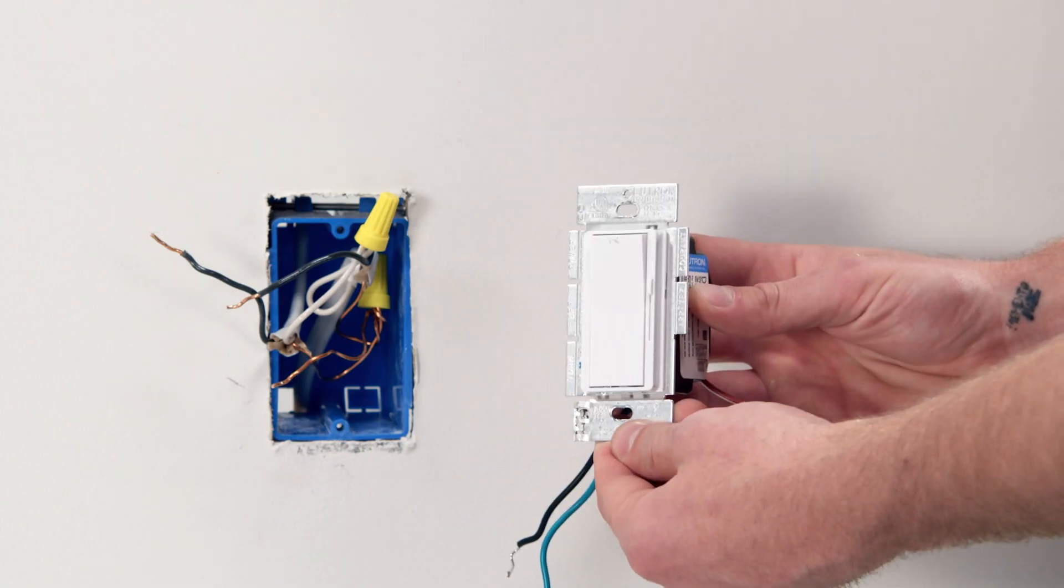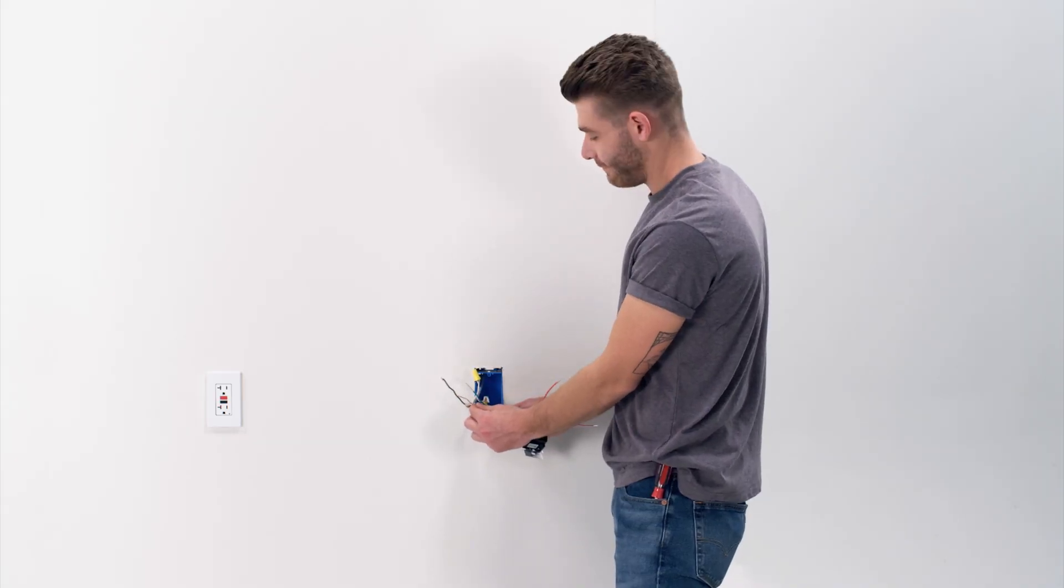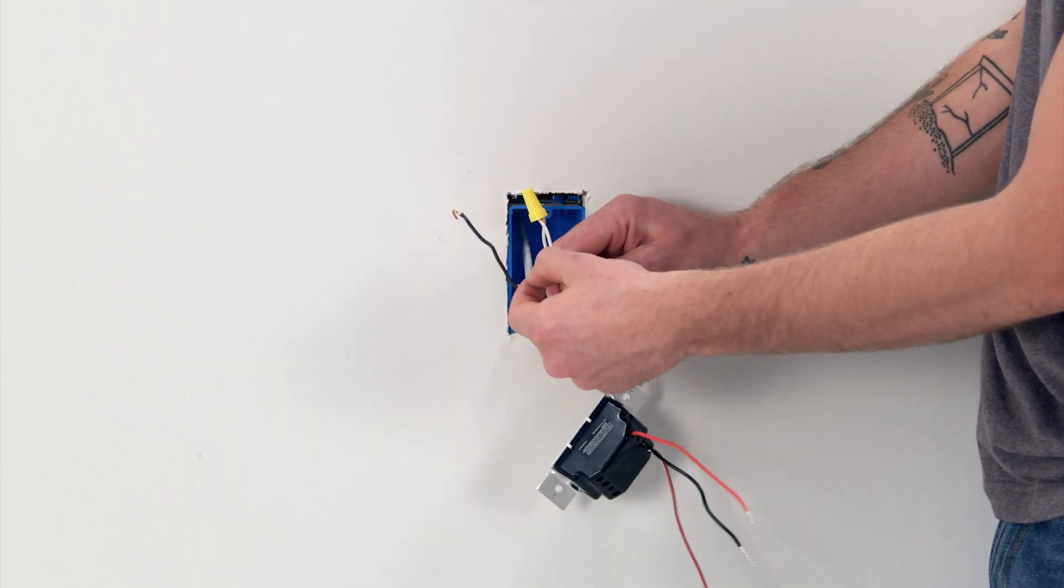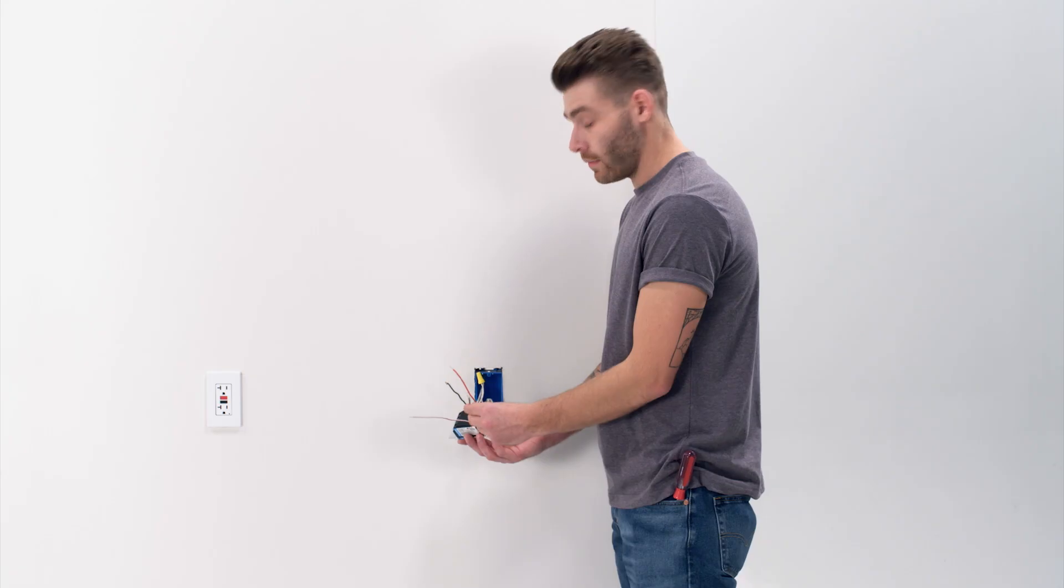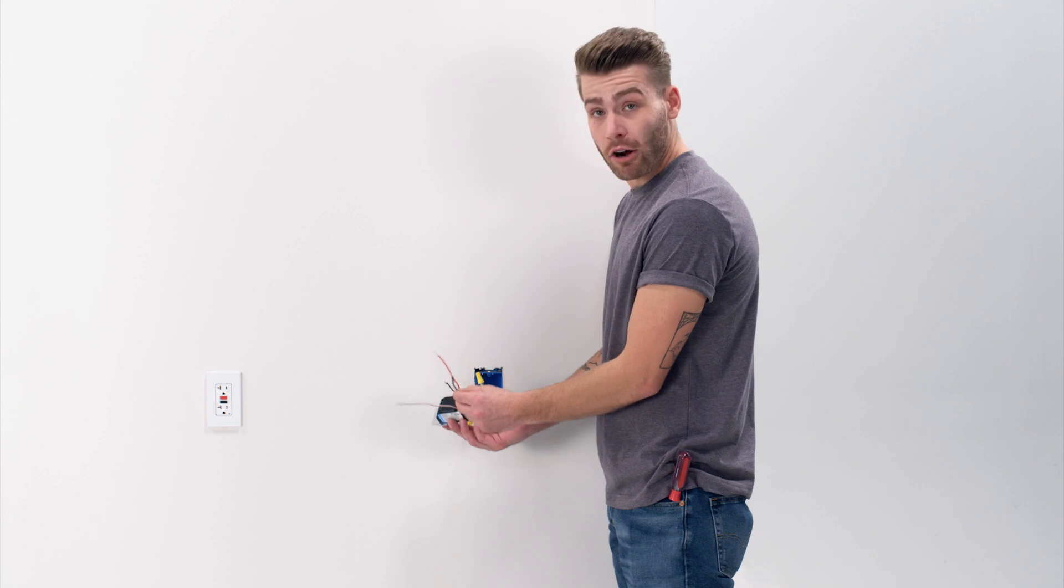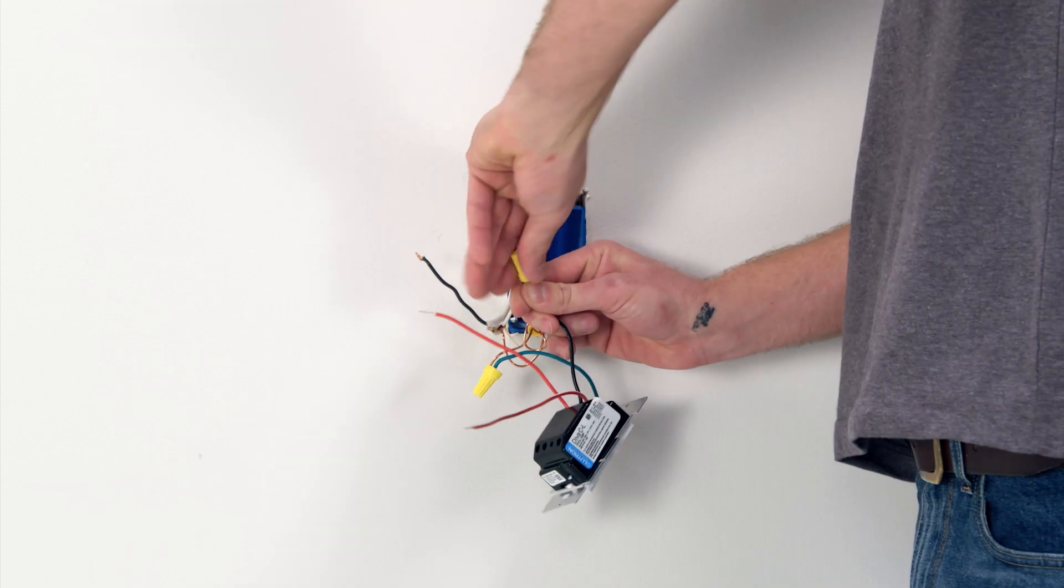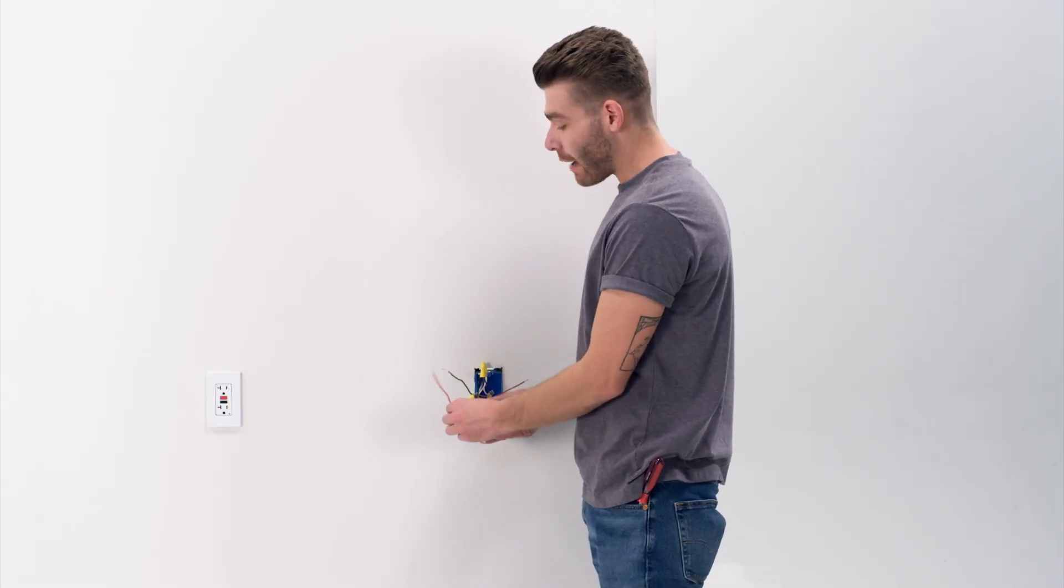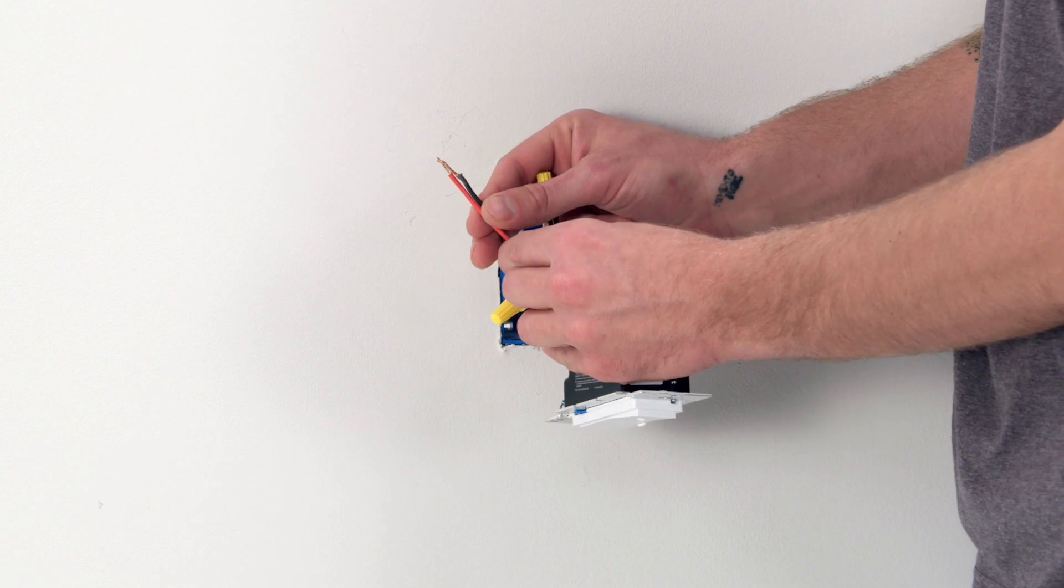And now it's time to install this new dimmer switch. First, ground to ground. And next, we'll take our black wire from the dimmer to the black lead wire from the wall. And finally, we'll attach the solid red wire from the dimmer to the black load wire coming from the wall.